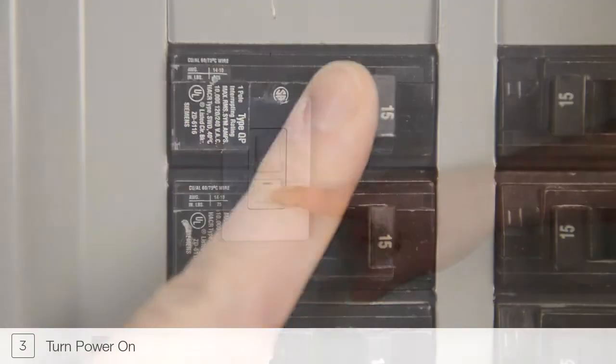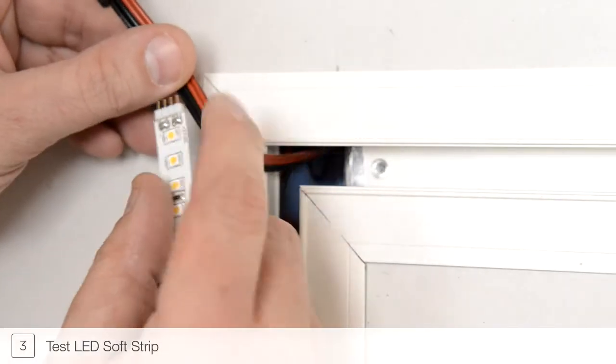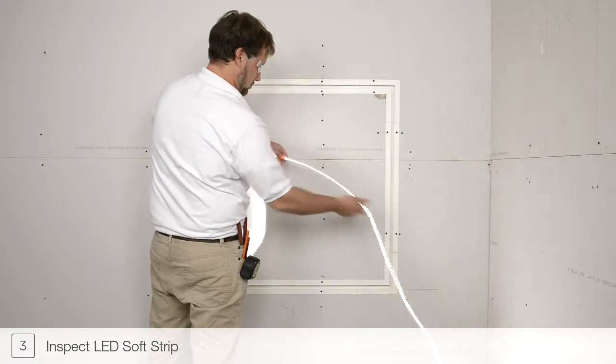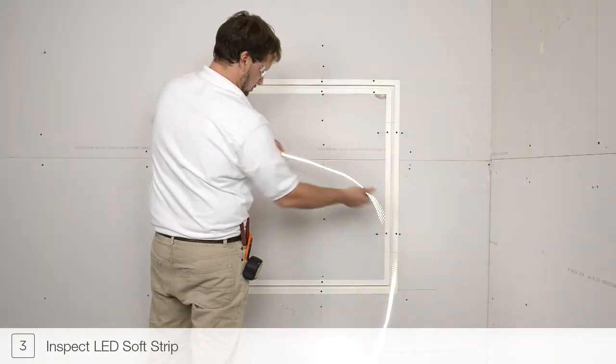Restore power to the junction box to test the LED soft strip. It is important to align the plus 24 VDC marking on the soft strip with the red wires of the power feed cable. Inspect the strip for any irregularities before continuing.